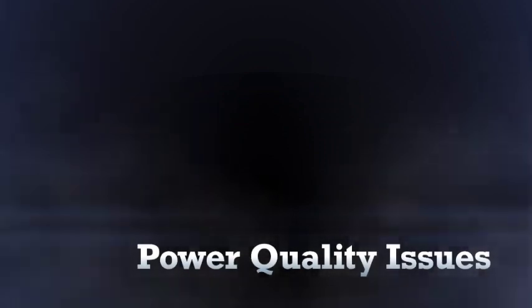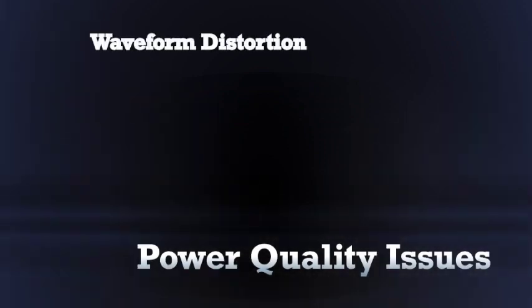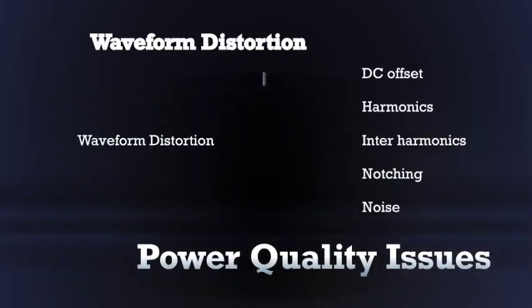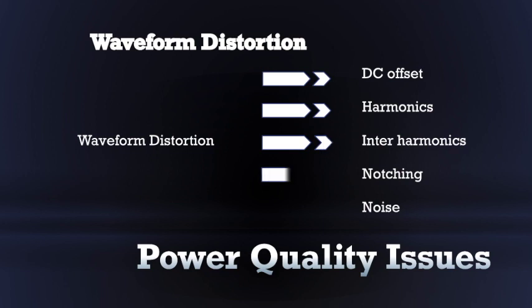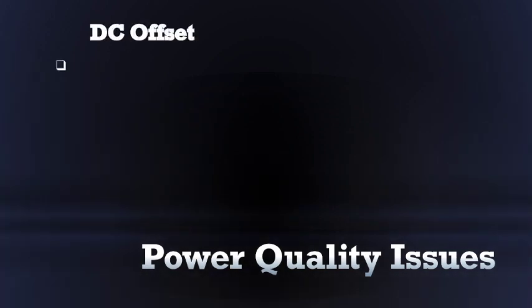Now the last category of power quality issue, waveform distortion. It includes DC offset, harmonics, interharmonics, notching and noise. Waveform distortion is defined as a steady state deviation from an ideal sine wave of power frequency. Now we will see the first one, DC offset.